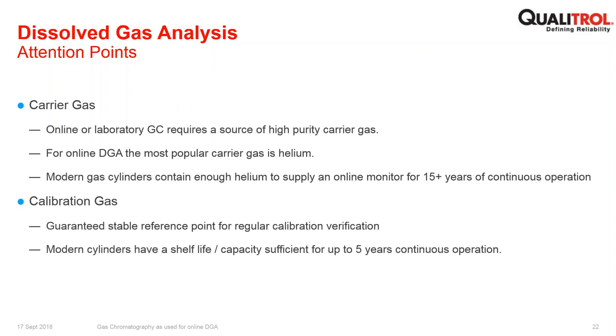Calibration gas is another thing that's required for online gas chromatography, along with all of the benefits that calibration provides. So accuracy and certainty, not just on the day of installation or in year one, but over the entire lifetime of the monitor. It provides certainty that you're operating off a known, physically traceable standard. It gives you confidence then to perform diagnosis and to make decisions about your transformer. Modern cylinders have a shelf life of the order of 5 years, and replacement of that cylinder will usually be dictated by the expiry date on the cylinder. So roughly 5 years.